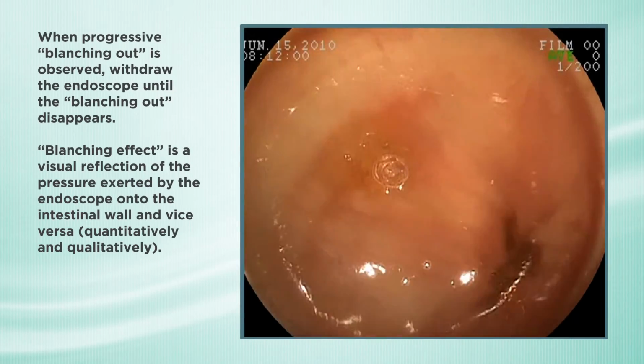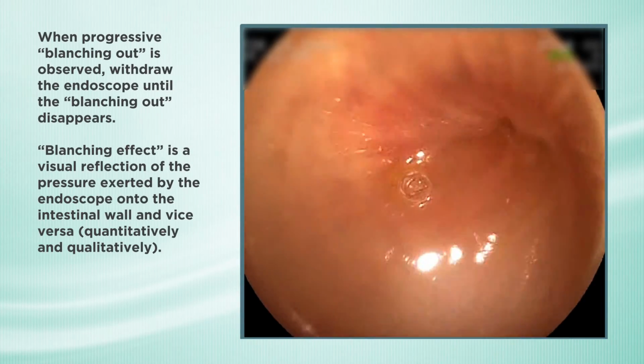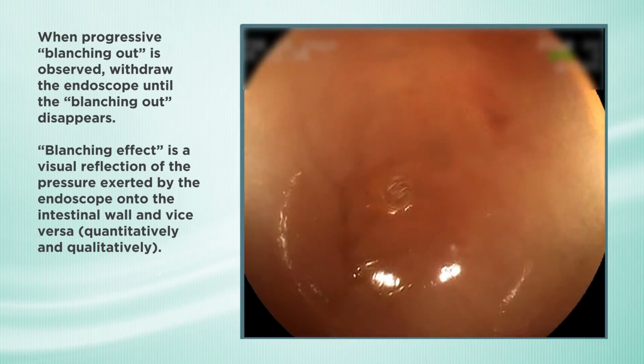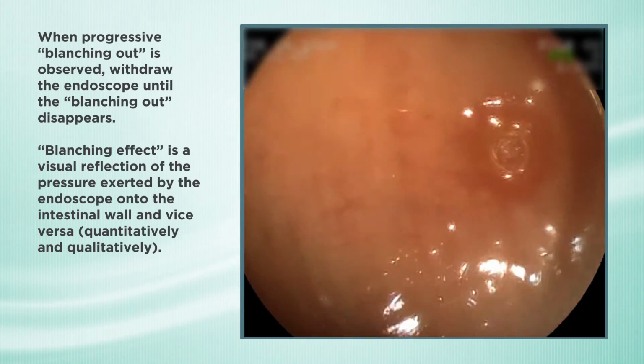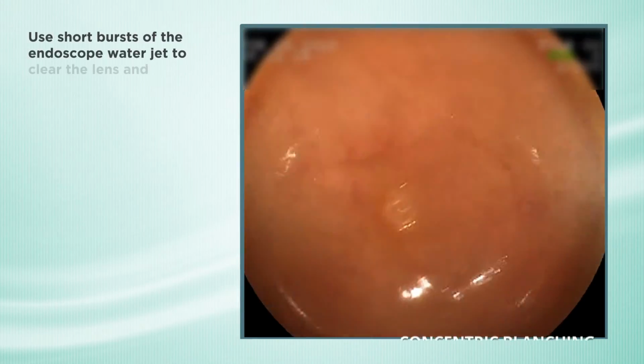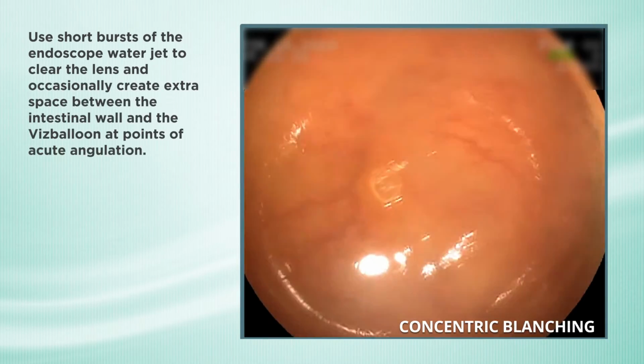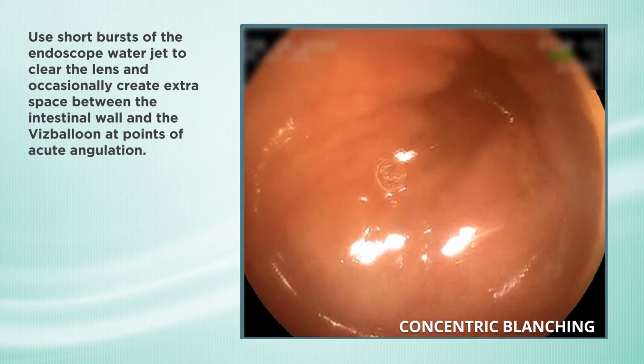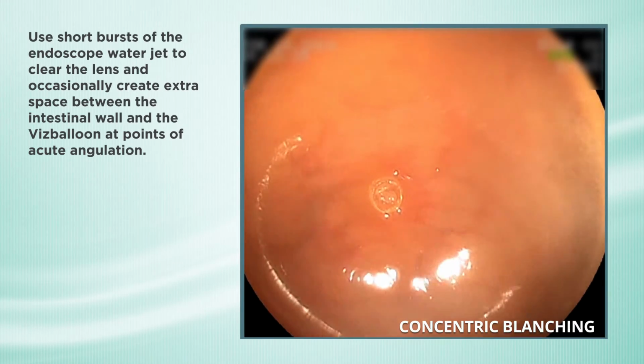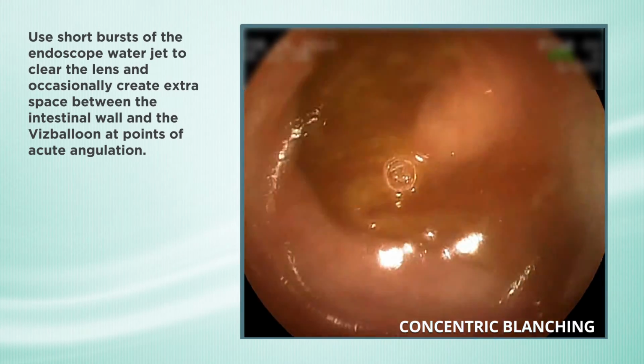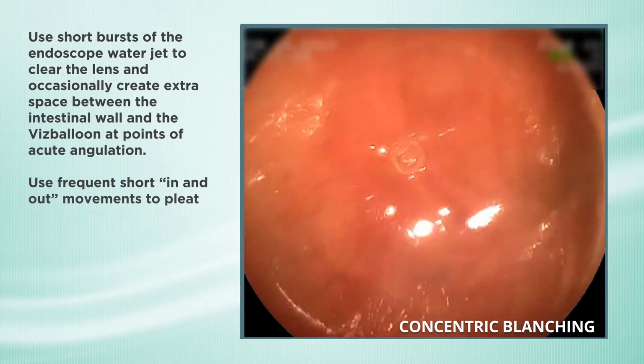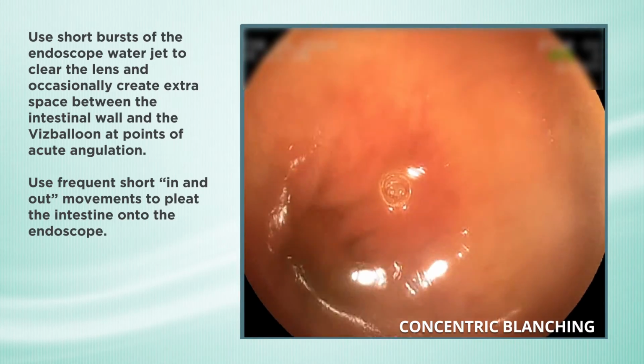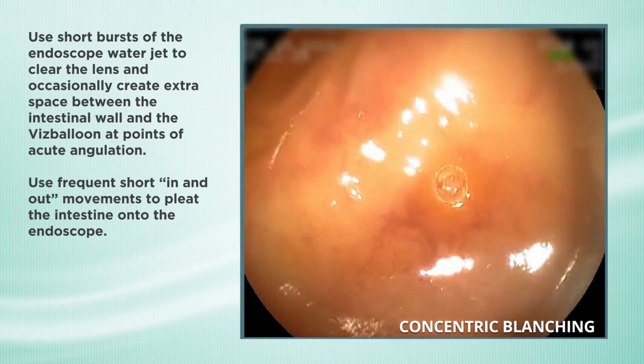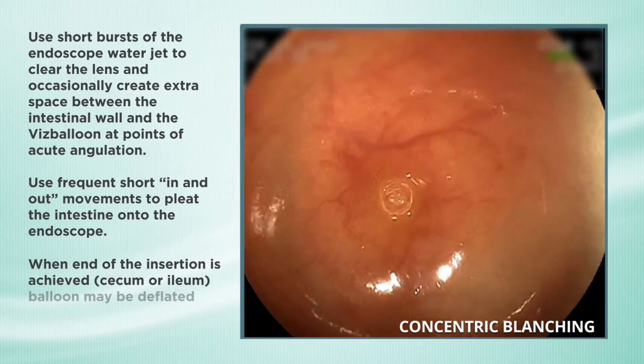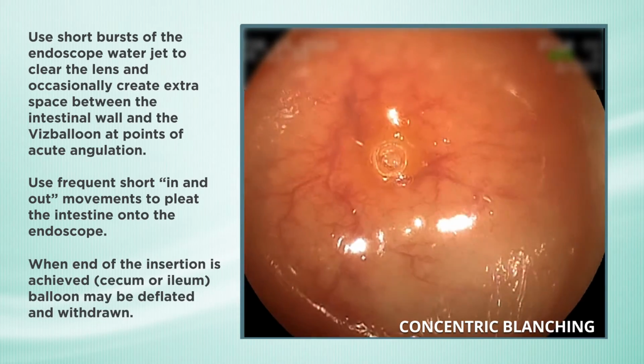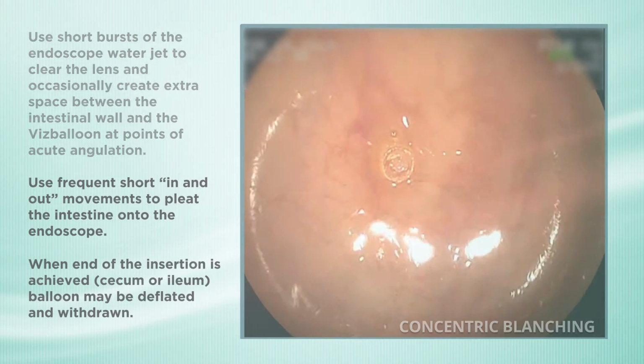Blanching effect is a visual reflection of the pressure exerted by the endoscope onto the intestinal wall, and vice versa, quantitatively and qualitatively. Use short bursts of the endoscope water jet to clear the lens and occasionally create extra space between the intestinal wall and the Vizballoon at points of acute angulation. Use frequent short in and out movements to pleat the intestine onto the endoscope. When end of the insertion is achieved, cecum or ileum, balloon may be deflated and withdrawn.